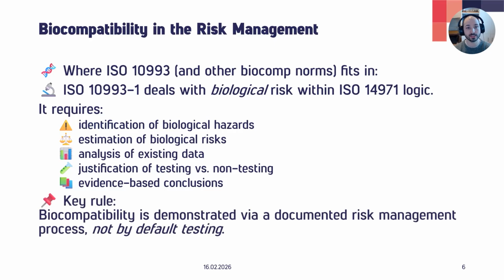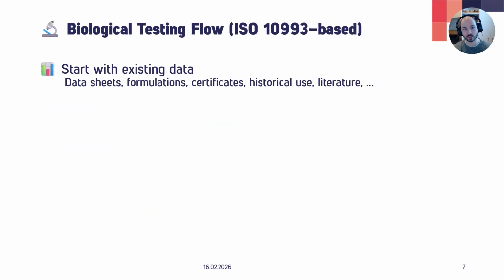So the key rule is always: demonstrate biocompatibility via a documented risk management process, not by default testing. So we do not have a checklist approach, where we just say, okay, we have this device, we need to do this test. Now, this is not how it works. We need to gather the data. We need to understand our device. We need to make a risk assessment. And then if we have gaps in the data, we need to close those gaps via testing. That is how this works.